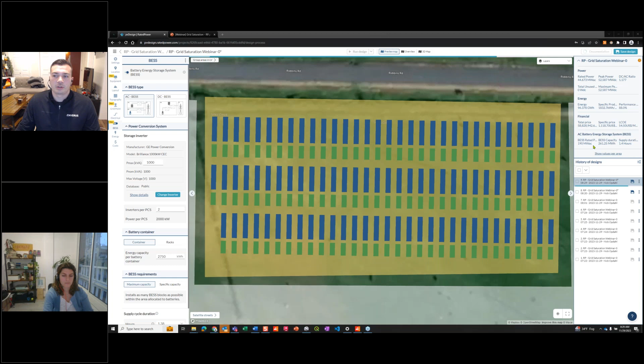So we select our inverters per PCS, then choose the battery container. I'd take a nameplate or cut sheet to pick whatever battery we choose, sizing the container by kilowatt hours, or if we want, we can get into the individual racks.